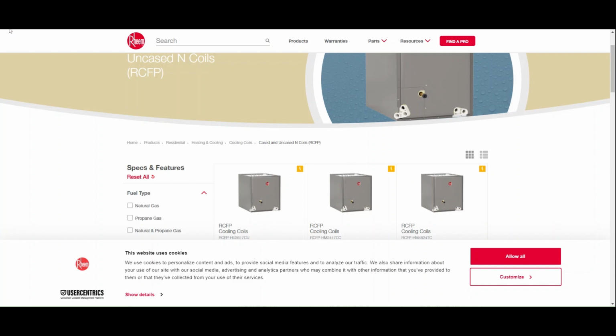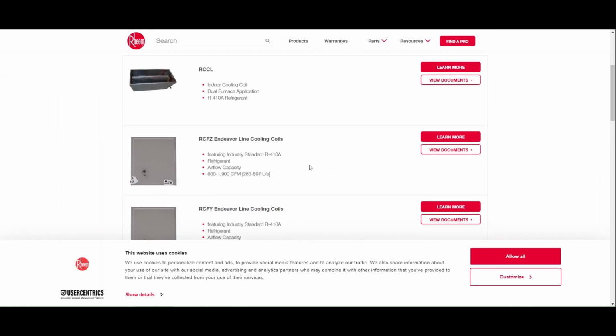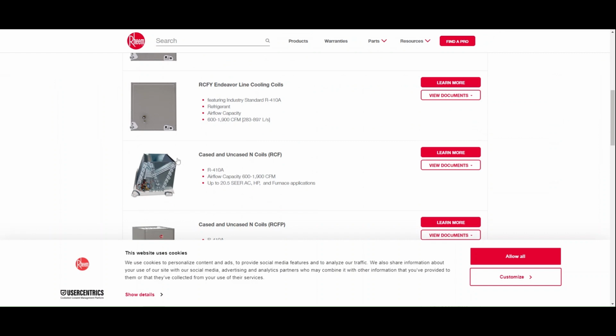Now I'm going to show you an uncased coil. So this is an uncased coil that you build into the existing tin work. So when you build this into the tin work, it's very hard to get at to clean it out, and you have to rely on a good installation or an installer that knows what they're doing, that blocks off the sides so the air doesn't bypass the coil and effectively not use the equipment correctly.